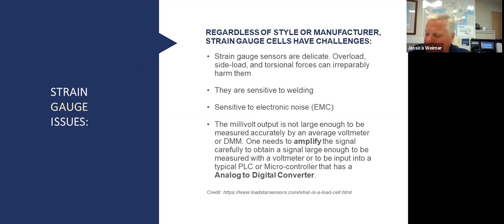In addition, because they create an analog signal, they're sensitive to ambient electric noise, otherwise known as EMC. So if you've got a variable speed drive in close proximity to a strain gauge load cell system, that can actually get picked up by the analog wiring and translated to the system and cause problems in readings. And finally, there's a statement here, and I actually took it from a website called LoadStarSensors.com, and they make strain gauge load cells.